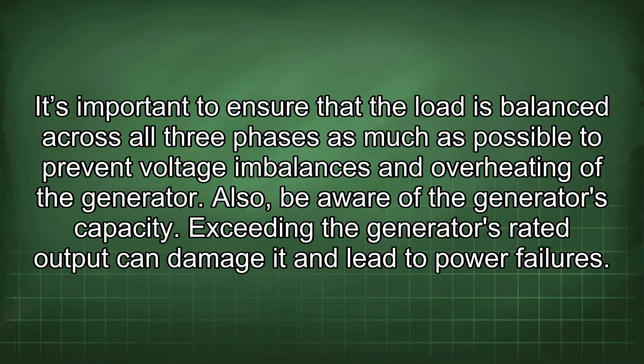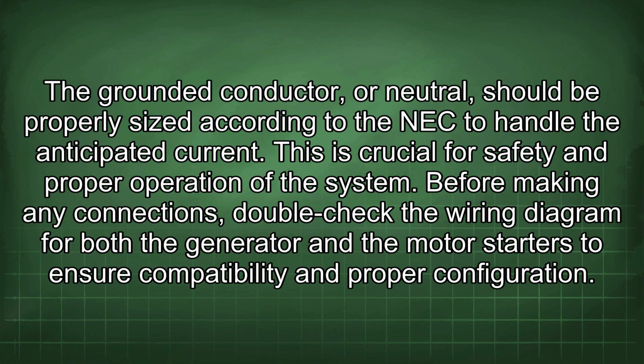Also, be aware of the generator's capacity. Exceeding the generator's rated output can damage it and lead to power failures. The grounded conductor, or neutral, should be properly sized according to the NEC to handle the anticipated current. This is crucial for safety and proper operation of the system.